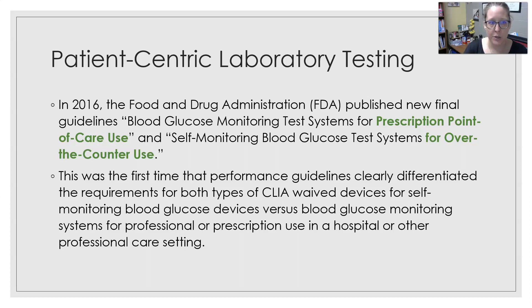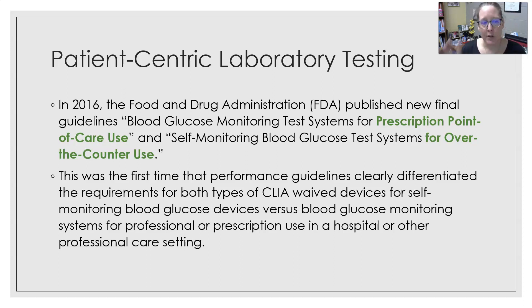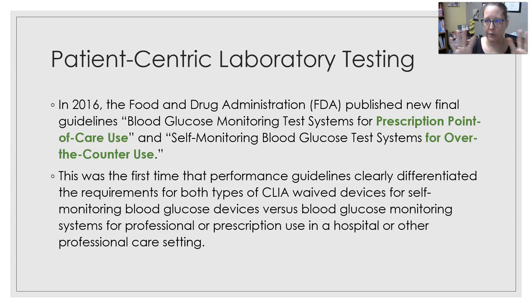In 2016, the FDA published new final guidelines called 'Blood Glucose Monitoring Testing Systems for Prescription Point-of-Care Use and Self-Monitoring Blood Glucose Testing Systems for Over-the-Counter Use,' differentiating between what is done in clinics and hospitals versus what patients do at home. This was the first time performance guidelines clearly differentiated the requirements for both types of CLIA-waived devices: self-monitoring blood glucose devices versus blood glucose monitoring in a professional setting such as a clinic or hospital.